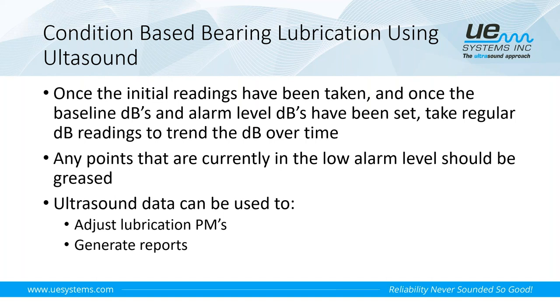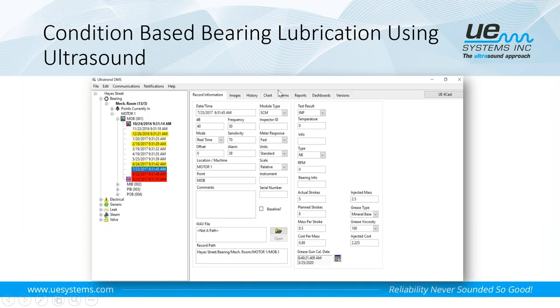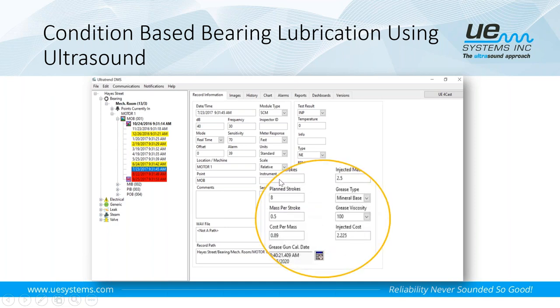So for each one of the applications in the DMS software, we have application-specific reports. You'll notice here, when you go into the DMS software, you'll see a reports tab here. Now for the bearing application, we have some lubrication-specific fields down here. And again, this is going to be information that will be pulled directly from your Ultraprobe 401, to where we know the actual number of pumps of grease. So if we did apply grease to a bearing, we can store that information on the grease caddy. When we set up the route, if we know the planned number of pumps of grease, now we can track and trend how much grease we're using, actual number of pumps compared to what was planned.